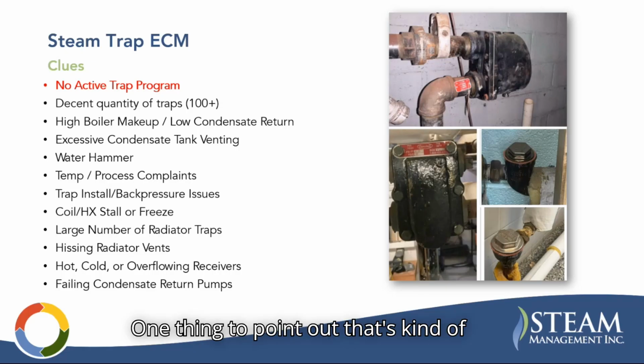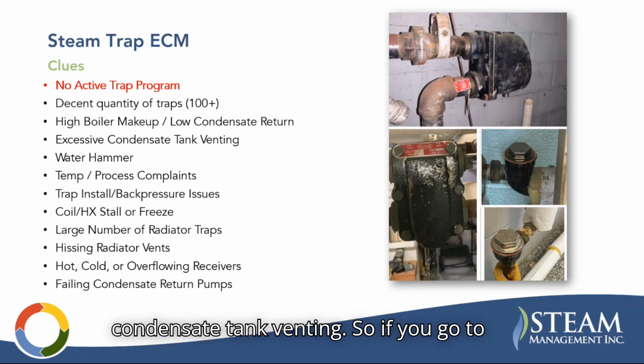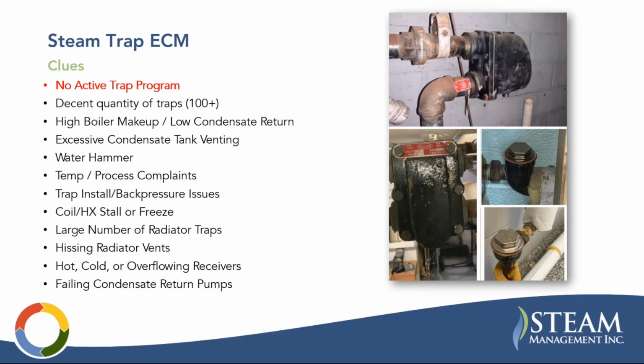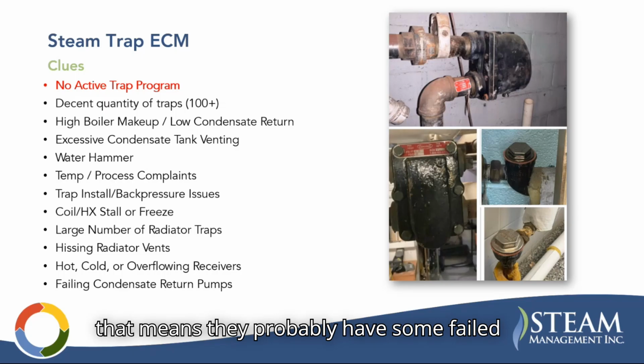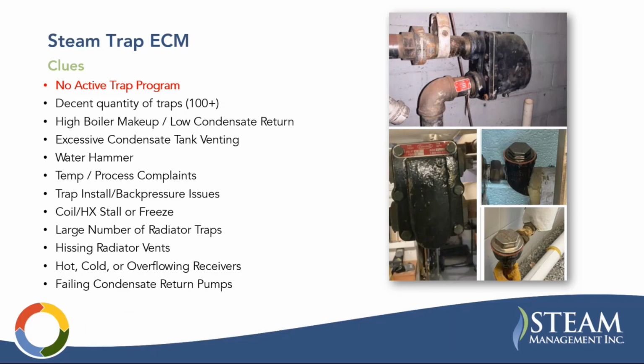One thing to point out that's easy to identify is excessive condensate tank venting. So if you go to a steam system and you see their condensate tanks, or even vents on the roof, just steam billowing out, that means they probably have some failed traps, and there's probably an opportunity there.